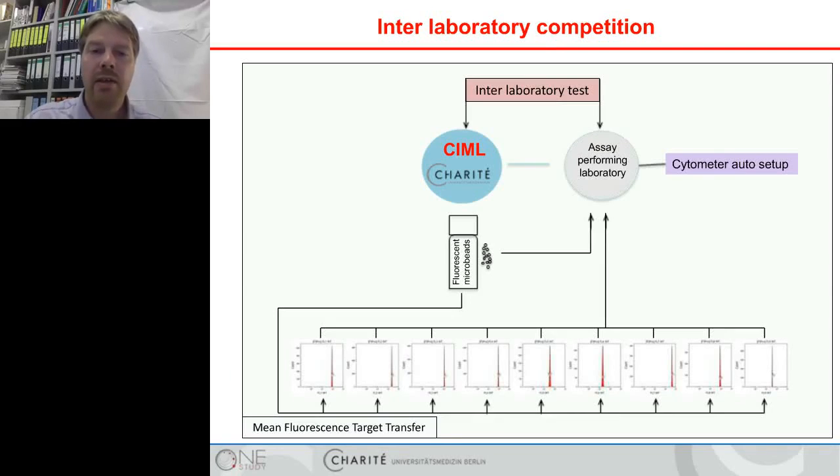After defining the target values, we provided all this information together with the information about the bead lot to the assay performing laboratories. Then we performed the cytometer setup via auto setup procedure at the assay performing laboratories, and then we did an interlaboratory comparison.